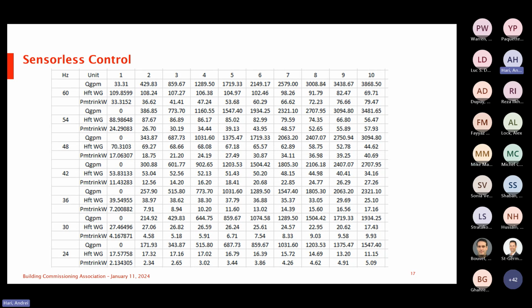No, it won't be recalibrated. We would just put the density factor against this data point. We typically test against water all the time, and then we add the correction factor if it's 10%, 20%, 30% ethylene glycol or propylene glycol. And that's a parameter. So to your point, you could have this pump in the field, and if the fluid changes, you're just changing the constant factor for the density of the fluid in the controller itself. It's actually a parameter that can be changed in the card. It's just something that we don't cover right now.